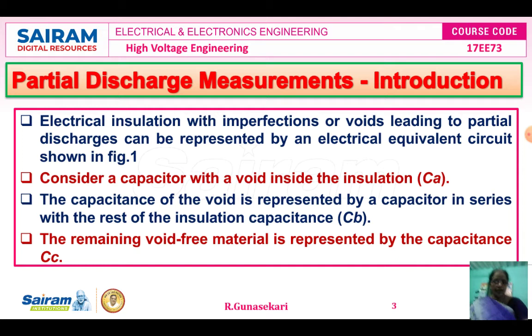If the sites of the partial discharges can be located inside an equipment, like a power cable or a transformer, it gives valuable information to the insulation engineer about the regions of greater stress and imperfections in the fabrication. Based on this information, the designs can be considerably improved.